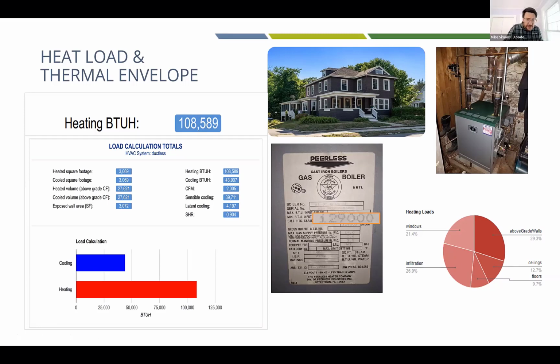You got it. Sometimes there'll be two different numbers. There'll be like a max and a min, or an input and an output, and the difference between the two would be the efficiency of the boiler. So sometimes if you open it up and look at the label, you'll see 100,000 BTUs input and 80,000 BTUs output, and that would be because the boiler is 80% efficient.